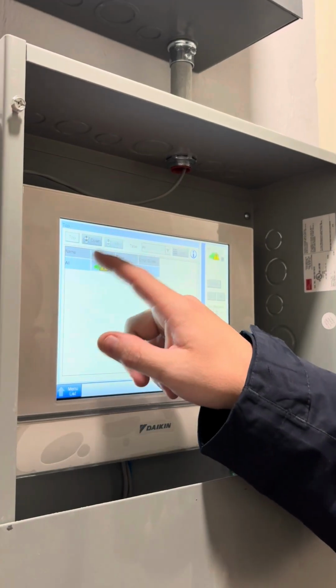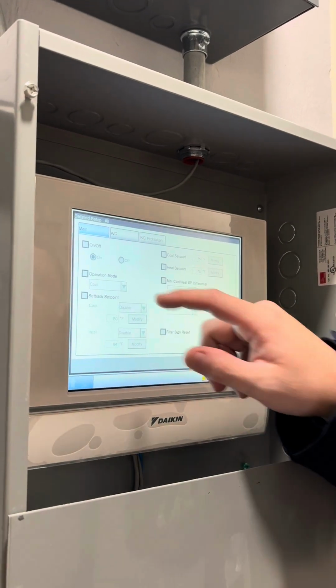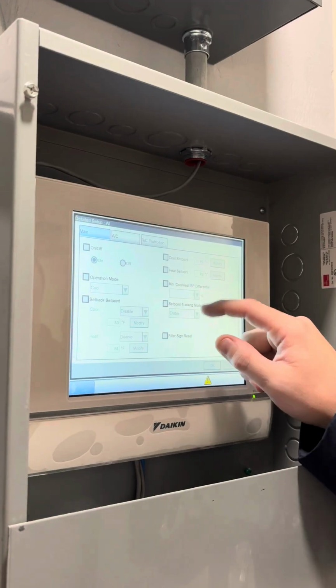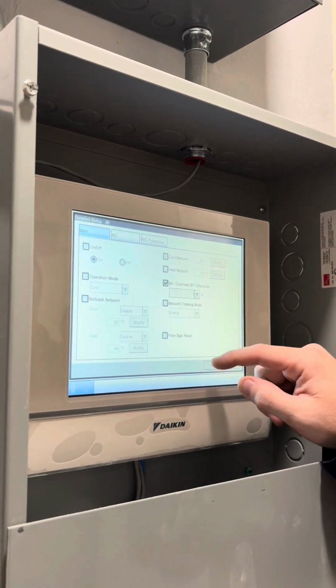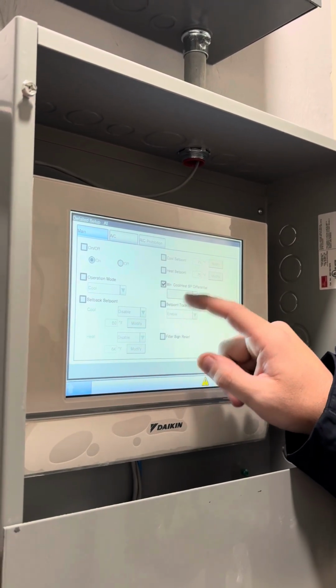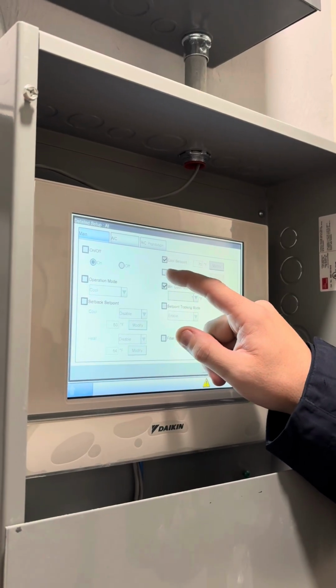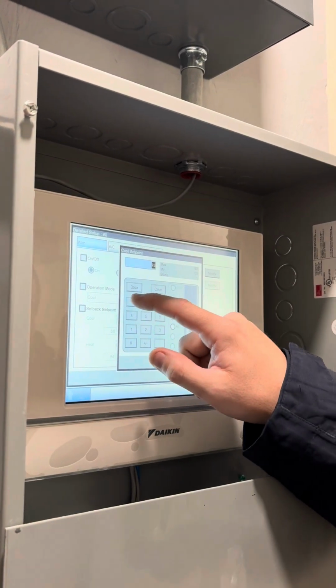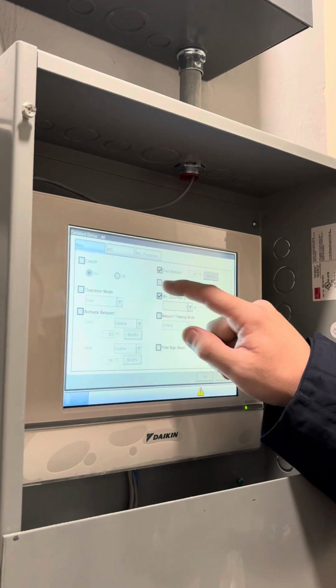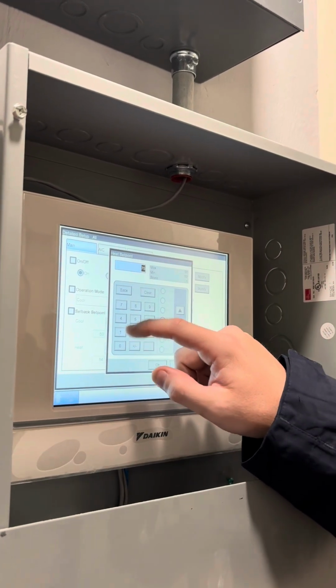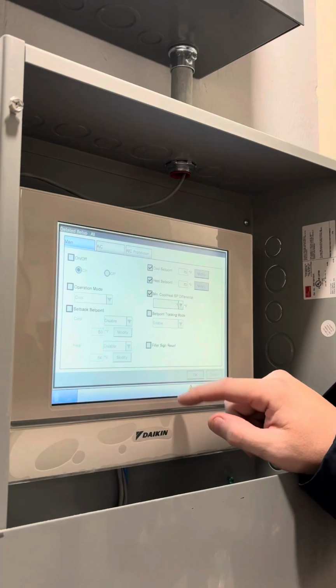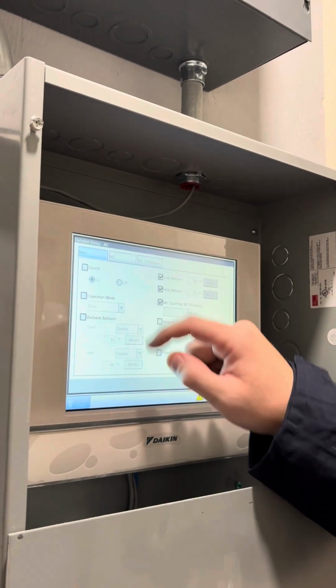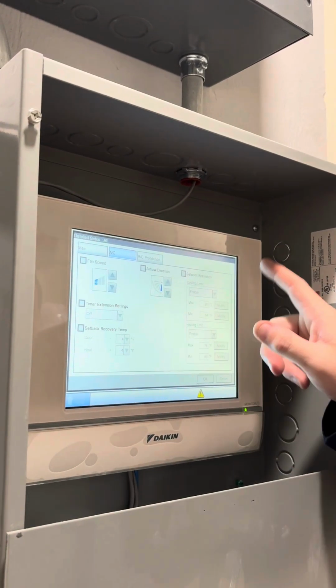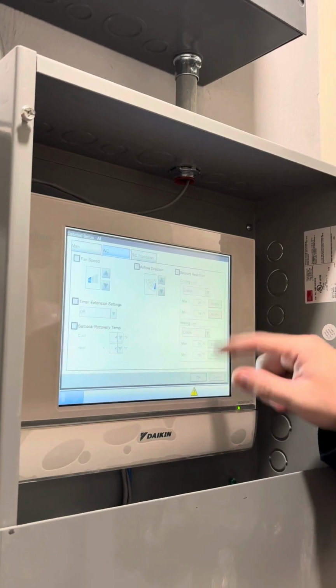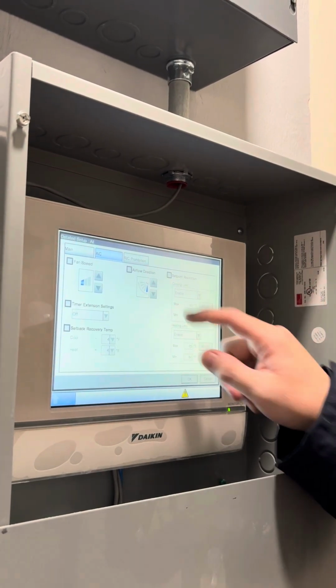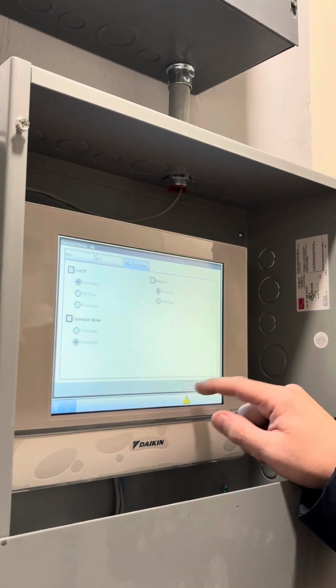So now, hold on, we have to go back to the top because I did notice something here. I want a minimum cool heat differential of 1 degree. So let's modify that one to 75 and heat down to 70. AC, change fan speed, and so on. The set point restrictions are still enabled, so they can only go within those limits. The RC prohibit is still the same.